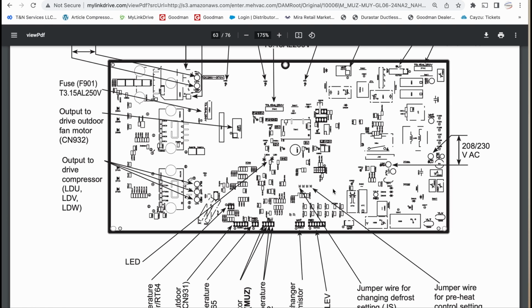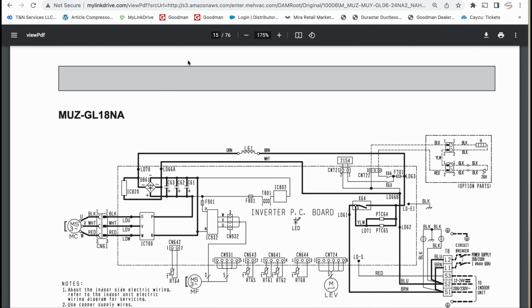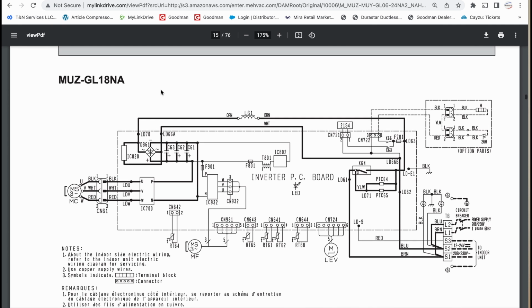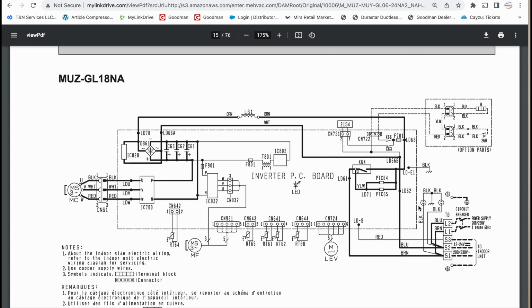Now let's go over to the wiring diagram. Let's look at it. Okay, so here's the wiring diagram. And right here is your L1, L2. That's your power coming in. It's going to jump down to S1, S2, and that's going to feed inside. But it's also going to come over here on this blue and brown wire, and it's going to feed up to LD61 and LD62.